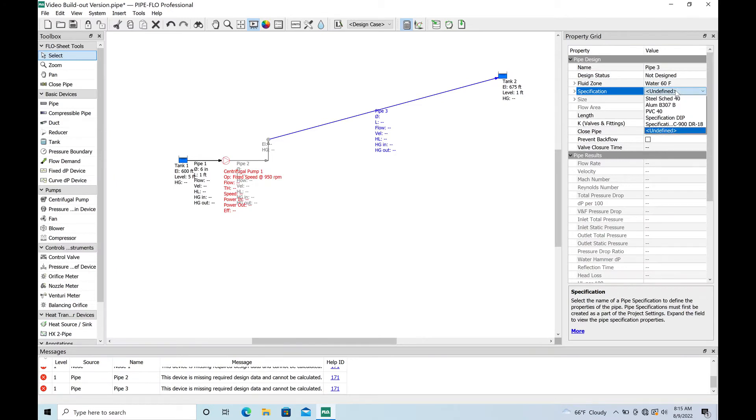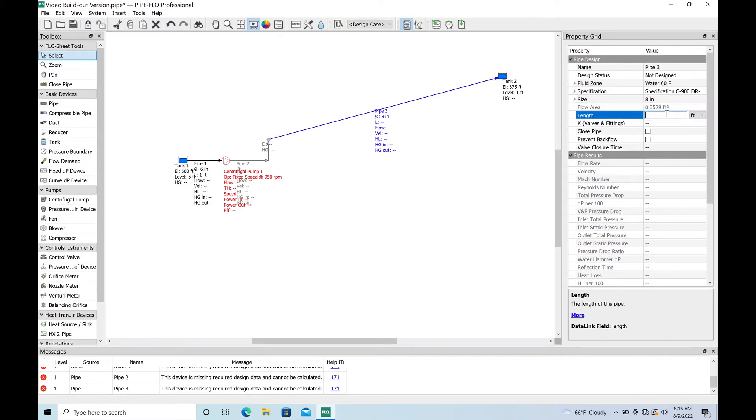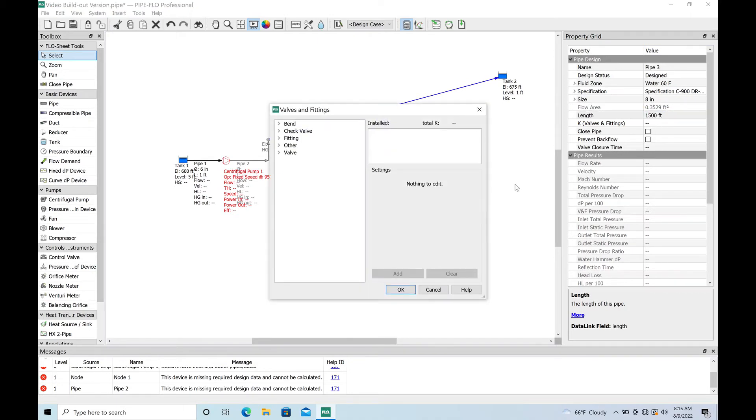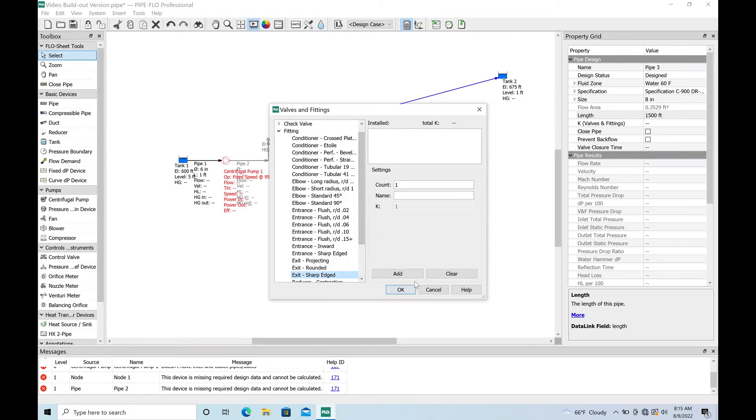All right, so here's our force main. This is probably the key component that's going to make a lot of difference on our head. It's going to be C900 DR 18 and it is going to be 8 inch. There's our flow area already populated. We'll say it's 1500 feet long and we'll go ahead and throw an exit loss. Just for fun it won't make a huge difference but I'll add that.